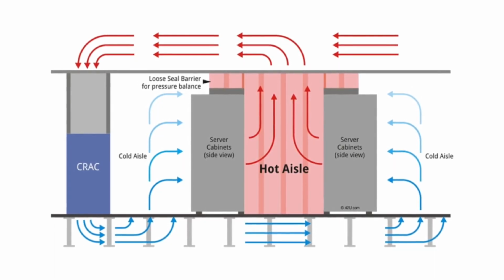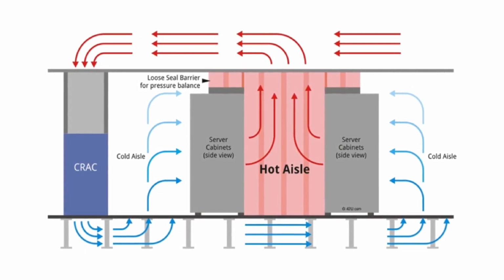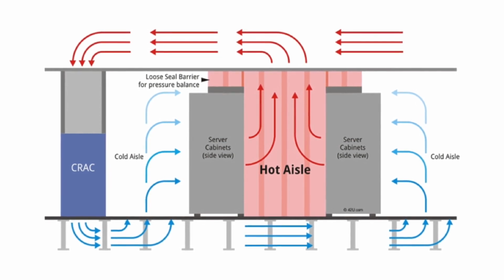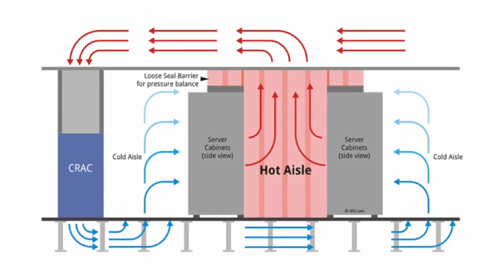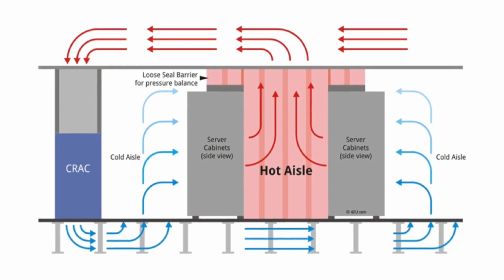So this is one of the key elements to designing data centres - they utilise this principle of hot aisles and cold aisles. Servers will be positioned in their racks back to back. You will have cold air coming in through the front of the server racks, going through the servers, into a hot aisle that is in between the two servers on the back side.